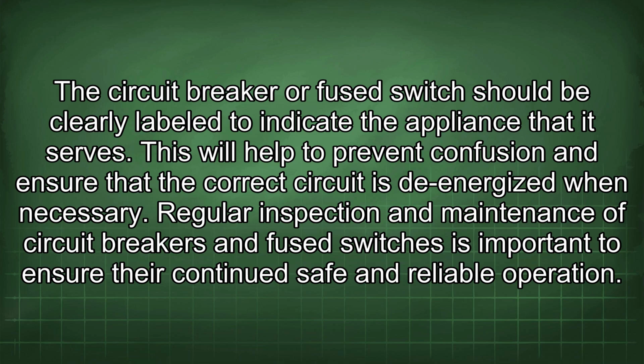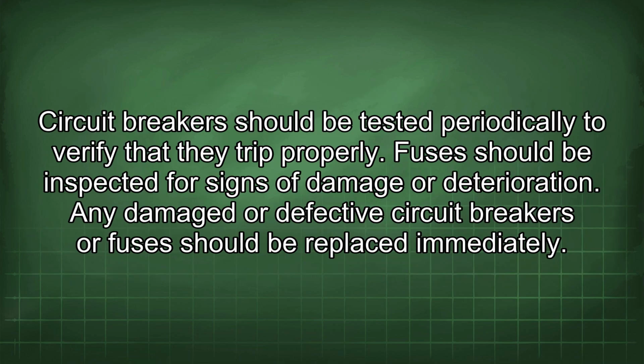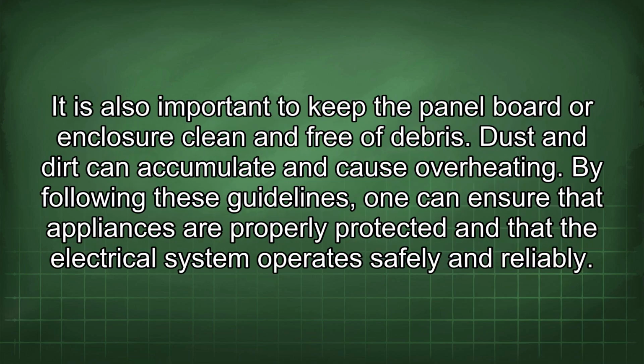Regular inspection and maintenance of circuit breakers and fused switches is important to ensure their continued safe and reliable operation. Circuit breakers should be tested periodically to verify that they trip properly. Fuses should be inspected for signs of damage or deterioration. Any damaged or defective circuit breakers or fuses should be replaced immediately. It is also important to keep the panel board or enclosure clean and free of debris. Dust and dirt can accumulate and cause overheating.